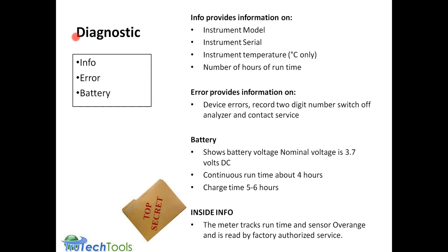In the diagnostic mode, which I believe is the last menu available in the menu screen, you have three submenus: info, error, and battery. On the info screen, you get the model and serial number of the meter, which is electronically embedded in it. It's also on the back label of the cover that we talked about before. It will also tell you the instrument temperature in degrees Celsius, which is important when you're doing some diagnostics and troubleshooting. The technician may ask you that. Then the number of hours of runtime.